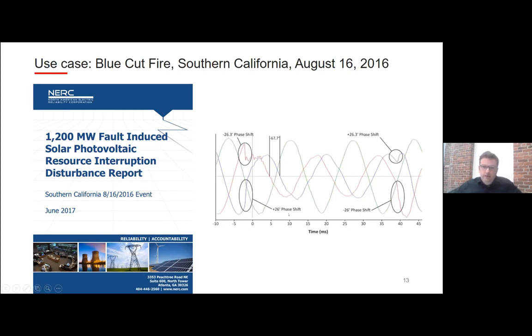The thing was that all the solar inverters detected this event as a low-frequency ride-through event. They started measuring below 57 hertz, even though the frequency was actually constant. It's just because of that fault it looked different, but the problem was the PLLs were poorly designed.